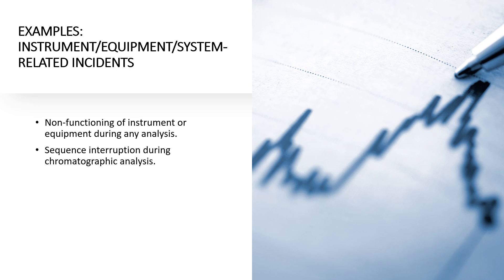Examples of instrument, equipment, and system-related incidents include: non-functioning of instrument or equipment during analysis — such as connectivity and communication failures, UPS failure, power failure, or operational software errors. Also, sequence interruption during chromatography analysis, resulting from power backup failure, pressure fluctuation, or column leakage. Additionally, system suitability failures — including similarity factor failure, resolution not achieved, asymmetry failures, theoretical plates not achieved, percent RSD of area failure, and retention time not achieved as per specification.